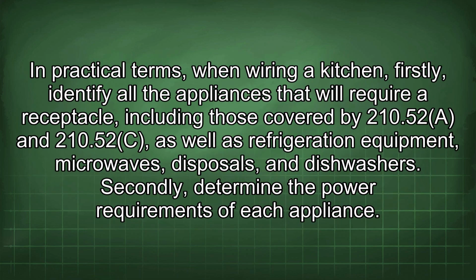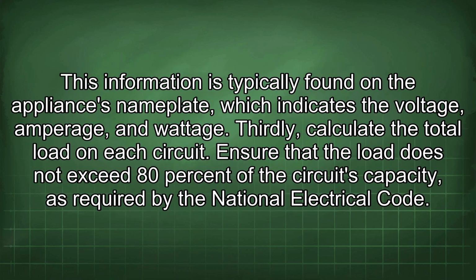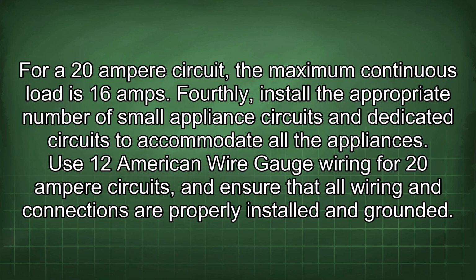In practical terms, when wiring a kitchen, firstly, identify all the appliances that will require a receptacle, including those covered by 210.52(A) and 210.52(C), as well as refrigeration equipment, microwaves, disposals, and dishwashers. Secondly, determine the power requirements of each appliance. This information is typically found on the appliance's nameplate, which indicates the voltage, amperage, and wattage. Thirdly, calculate the total load on each circuit. Ensure that the load does not exceed 80% of the circuit's capacity as required by the National Electrical Code. For a 20-ampere circuit, the maximum continuous load is 16 amps.